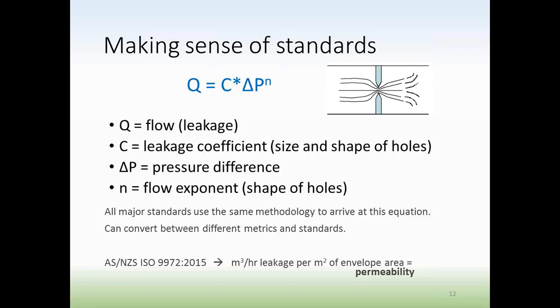And all of those standards mentioned do the same thing, which is to derive this equation: Q, the amount of leakage, equals C, the leakage coefficient, times delta P, the pressure difference, to the nth power, where n is a flow exponent that's just related to the geometry of the holes. So all the major standards use that same methodology to arrive at that equation, and once you have that, you can report the leakage at 75 pascals, 25 pascals, 50 pascals, and convert between the different standards.